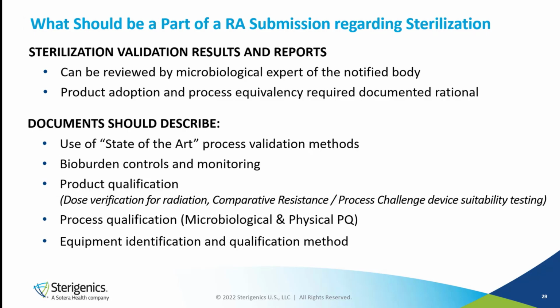In terms of regulatory submission, you have to be prepared that your submission is going to be reviewed by microbiological experts from the notified body side. And here I wanted to say one word regarding product adoption. When you have to do a resubmission for a product adoption, what is a product adoption? It's when you have validated a product family with the EO cycle, a validated EO cycle, for example. And when you want to add a new product, you need to have documented evidence that your product is not going to be more resistant than the main product, the worst case product of your product family.